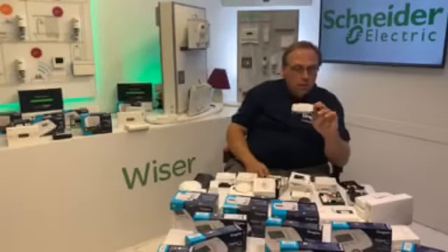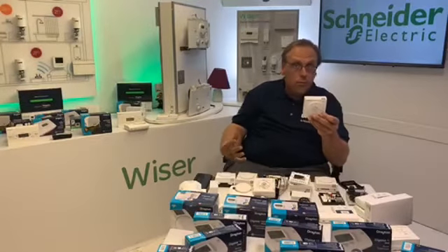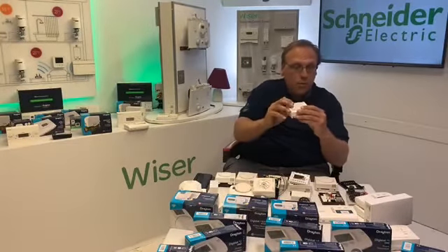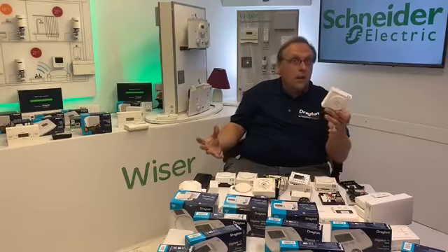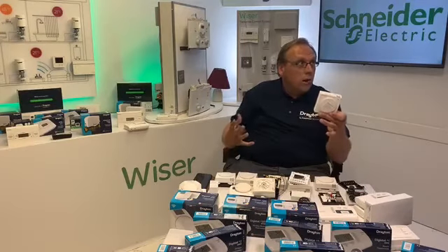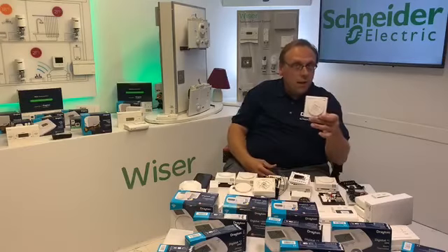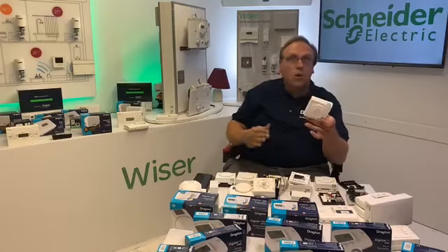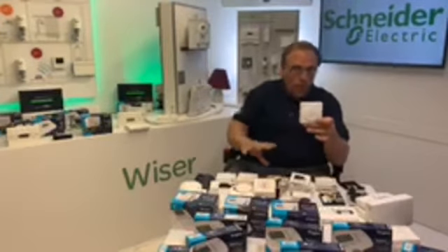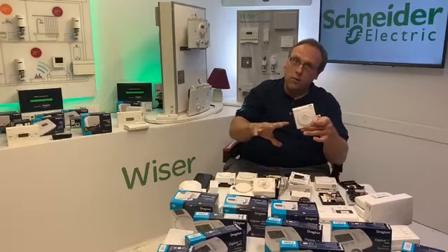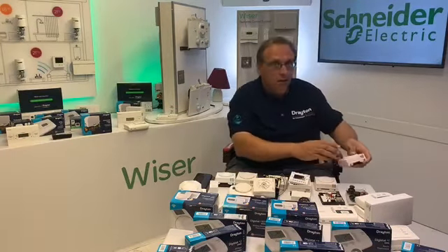And this, again, the wiring is like an RTS 4, so it is volt free, so it's a 4-wire thermostat. But the difference with this is it's got a minimum setting of 16 degrees. So if you're fitting it in a care home or somewhere where you've got to make sure that the temperature doesn't drop below 16, you fit the RTS 10, and you know even if you set it down to minimum, you won't go below that 16 degree limit. But in terms of the wiring, it's volt free, very much like the RTS 4 and the RTS 9. So that really takes care of the RTS range.